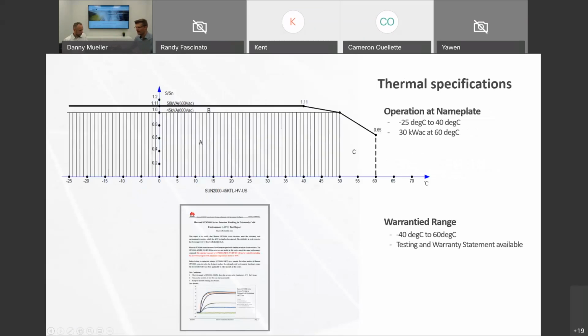Talking about cooling, the thermal operation window of a passive cooled inverter is absolutely key for the environment you deploy that inverter in. Most of those inverters for commercial rooftop systems are directly located adjacent to the array to fulfill the rapid shutdown requirements. In our case, about 1 meter, since it went down from 3 meters to 1 meter. And since those units are exposed to the elements, they typically need to have a wide enough operation window from a temperature perspective to not curtail based on over temperature.